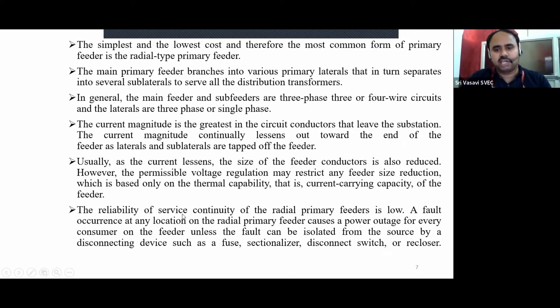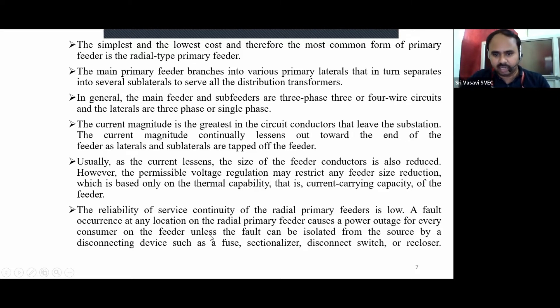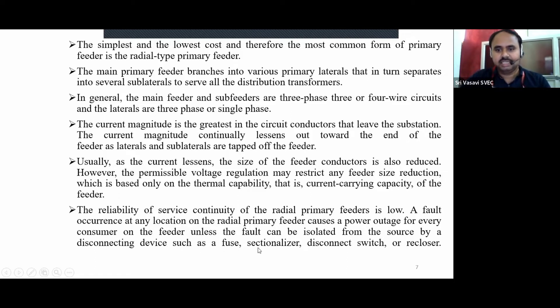The reliability of service continuity of radial primary feeders is low — this is a major drawback. A fault occurring at any location on the radial primary feeder causes a power outage for every consumer on the feeder, unless the fault can be isolated from the source by a disconnecting device such as a fuse, sectionalizer, disconnecting switch, or re-closer.